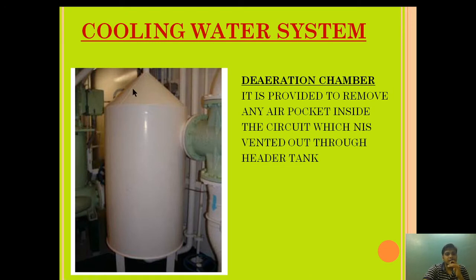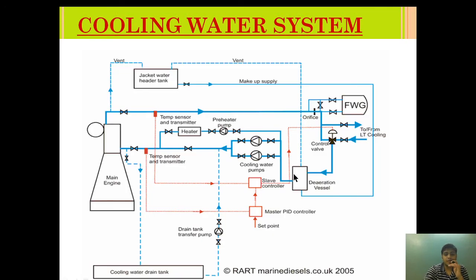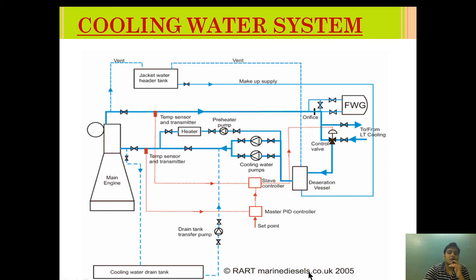The de-aeration chamber is a dome-shaped fitting provided just before the pump inlet so that any air pockets in the system can be removed, preventing cavitation. The main purpose of de-aeration is to vent any air pockets out through the header tank. As the temperature of liquid increases, the chances of vapour formation and cavitation also increase, so de-aeration vessels ensure that any air pockets formed are vented out.